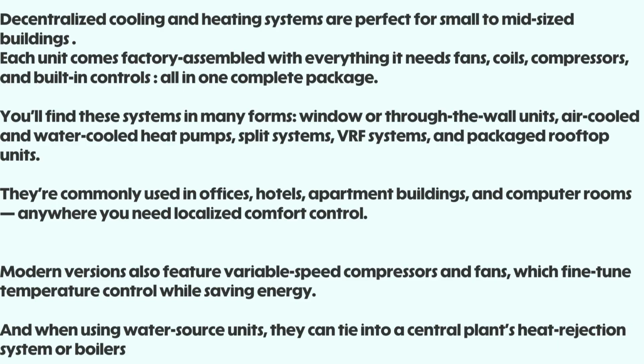Modern versions also feature variable speed compressors and fans, which fine-tune temperature control while saving energy. And when using water source units, they can tie into a central plant's heat rejection system or boilers, providing an efficient and integrated solution for year-round comfort.